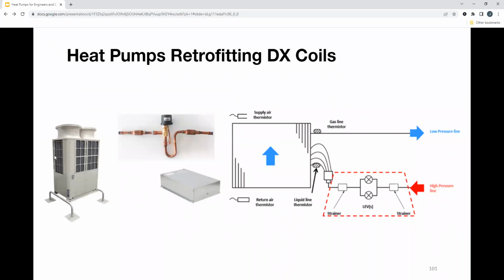So what do we need for this? You have your heat pump right here, placed on the outside. Typically it's air source, but you can do these applications with water source, right? And then you have your LEV kit or your LEV controller, more or less. What that's made up of is your LEV here, with strainers on the side. An LEV, or linear expansion valve, is located in all of our outdoor units. It adjusts in 2,000 different positions, over about a quarter of an inch. It modulates the pressure of the refrigerant to get the precise temperature that it needs. We're basically taking that out of a fan coil and using it here to control a DX coil. It also comes with 4 thermistors: supply air, return air, and then your gas line and liquid thermistors. And every LEV comes with a control box.